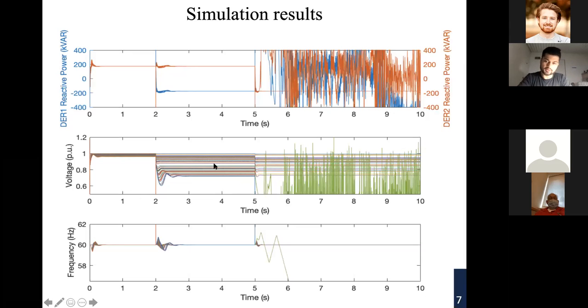Okay, so these are the results. If you look at the first graph, the left graph shows the DER1 reactive power, and the blue line, which is overlapping with the orange line. The blue line is DER1 reactive power, and the orange line is DER2 reactive power. As you can see, at first, before the attack, they were both injecting reactive power. The 0.44 PU of reactive power corresponds to 200 kVAR when you have a 400 kVA system. So you're injecting 200 kVAR at first, before the attack.